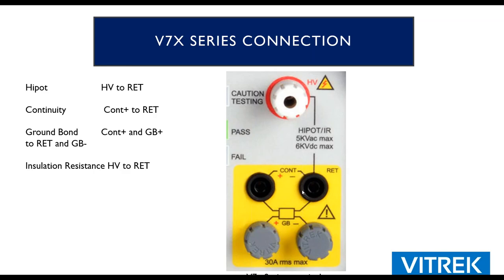terminals on one side of the circuit and the continuity minus and ground bond minus terminal on the other side of the circuit. The 4-wire measurement allows you to null out any voltage drop in the test leads, which is very important when you're trying to make precise measurements, especially those below 100 milliohms or so.